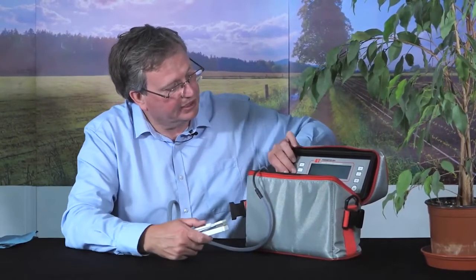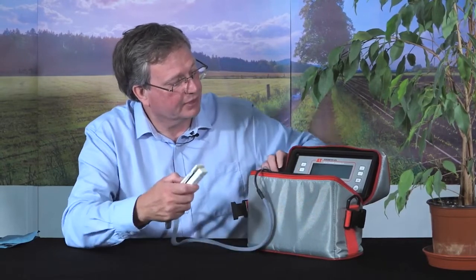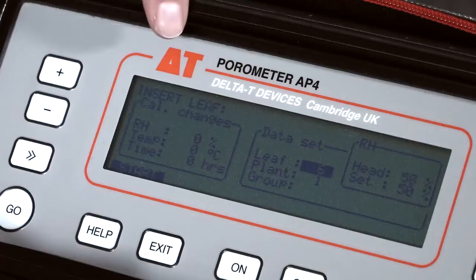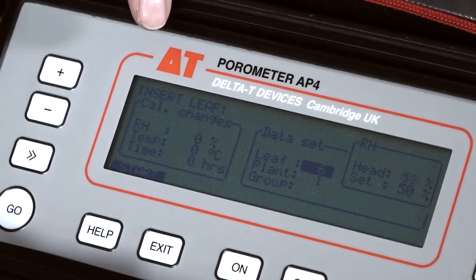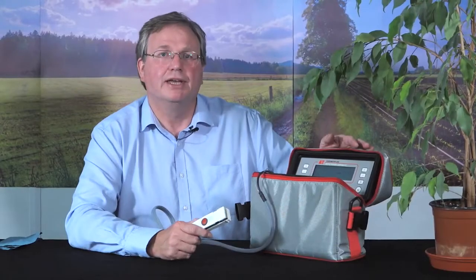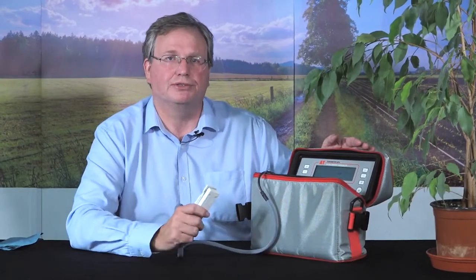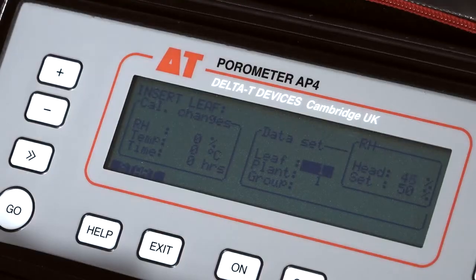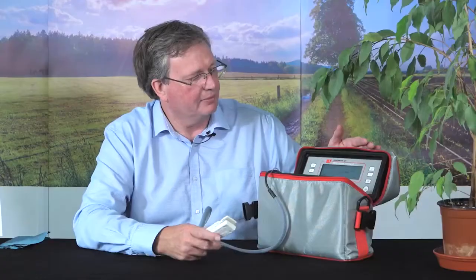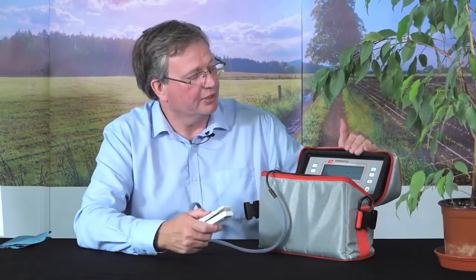So we're going to select the read function now. On the screen, on the left-hand side, we've got the prompts whereby the Porometer will tell you whether or not the humidity or temperature has changed too much since the last calibration. Not surprisingly, it's 0. There's been no change in temperature or humidity. On the right-hand side, there's the ability to change the leaf number we're measuring or the plant number, and to add a name for the group. So the group name could be control or treatment 1 or treatment 2. Once you're happy with the settings there, we're going to start the reading.